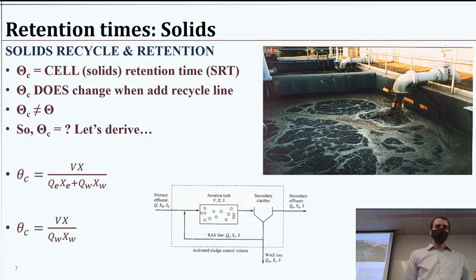The solids, however, do change, and I believe this is an image of recycling sludge back into an activated sludge chamber. So the solids, or cell, retention time, sometimes people call it, and our book has theta C. I'm using that because that's what they used. So theta C, the cell retention time, also known as SRT. Okay, so this SRT, the solids retention time, does change when we add this recycle line, and that's something we need to account for.